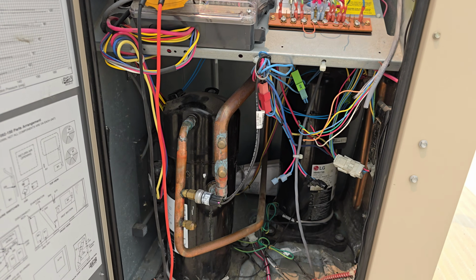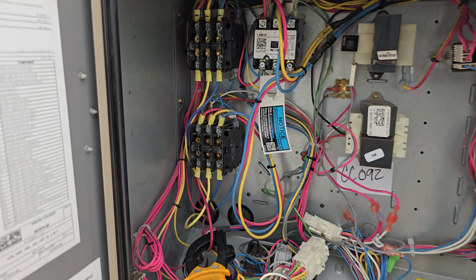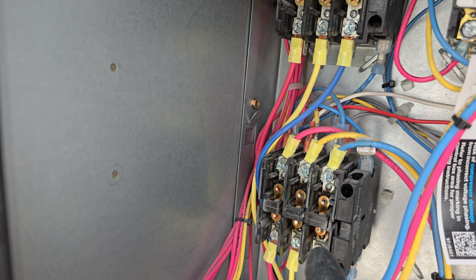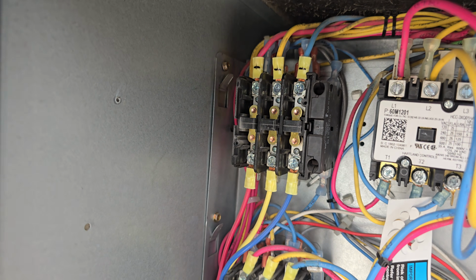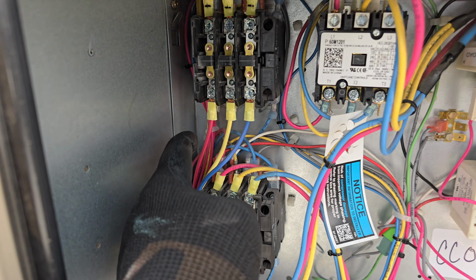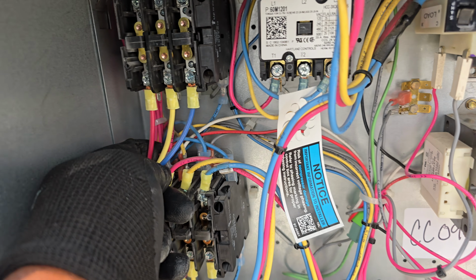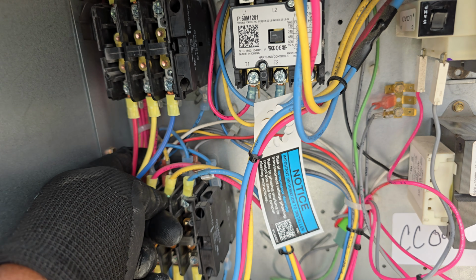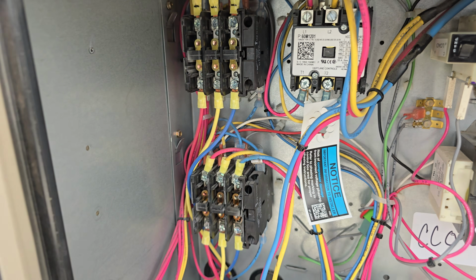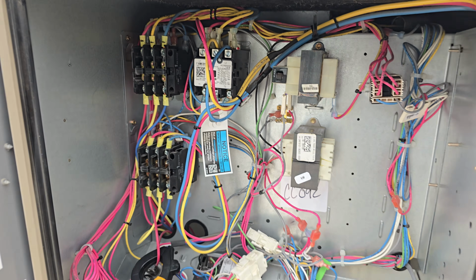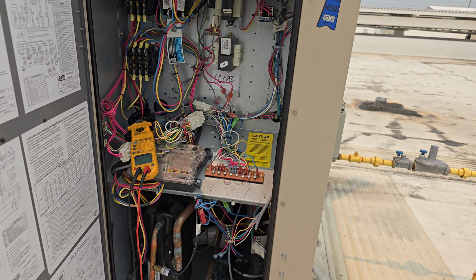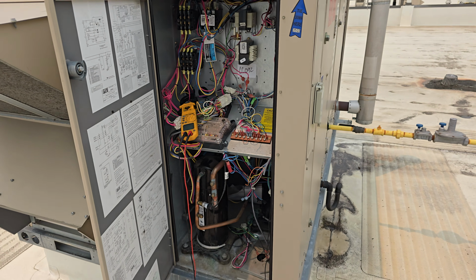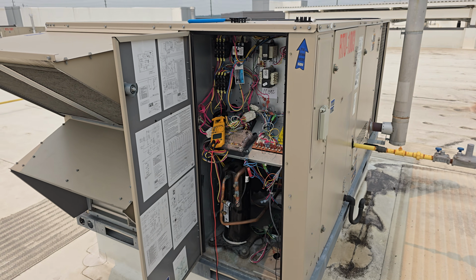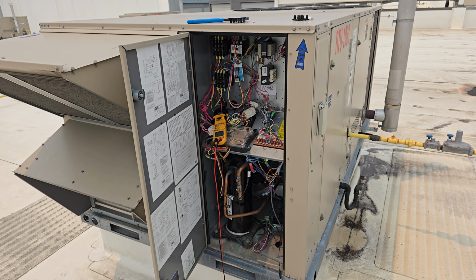Bring the second compressor on, and if it holds, then it means this contactor might be pulling this other one. Well, again, that's what I'm going to do. I'm going to have to disconnect my low voltage wire here so that it won't energize, and allow that unit to energize. So that's what I'm going to do. Please stay tuned and don't go away. We'll see what's happening here.